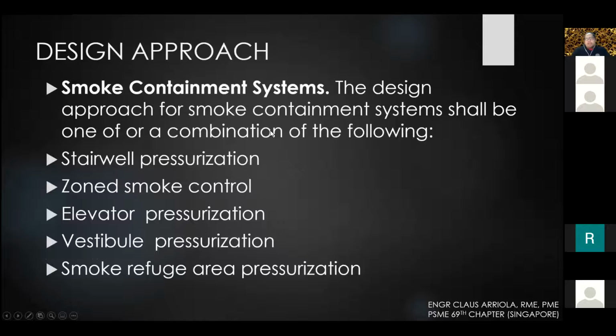Okay, what are the design approaches? How will you approach the smoke containment system? The design approach for a smoke containment system shall be one or a combination of the following. So we have stairwell pressurization, zone smoke control, elevator pressurization, vestibule pressurization, and smoke refuge area pressurization.